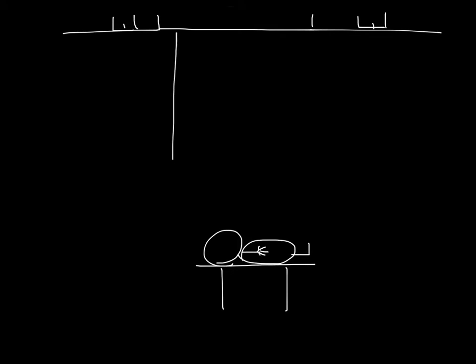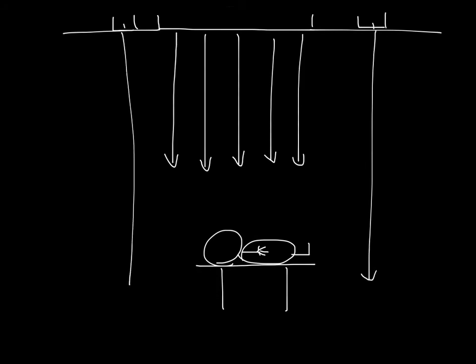So we have unidirectional non-aspirating flow out of the laminar flow diffusers. And out here with the air curtain, we have a higher velocity flow creating a barrier to the outside.